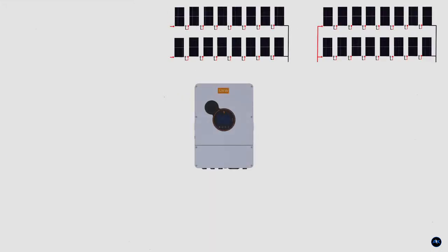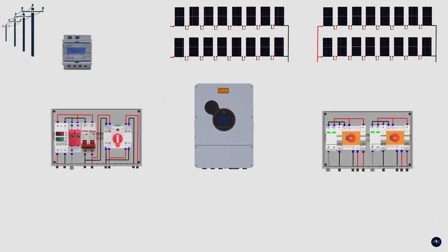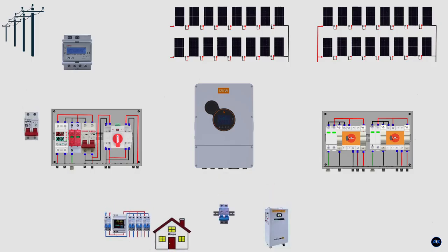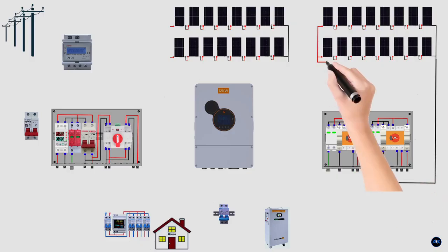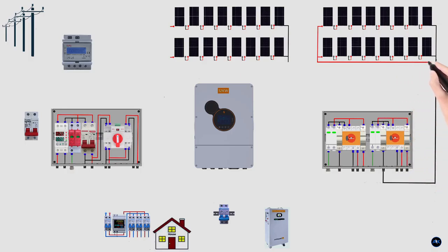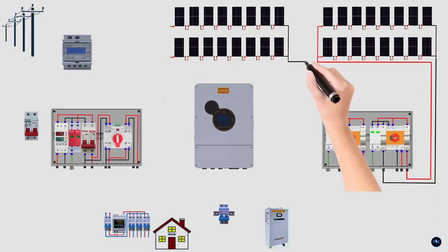Let's now connect the entire 12 kilowatt solar system step by step, starting from the solar panels and ending at the house loads. I'll explain this in a simple way, so even beginners can follow the full wiring logic safely. First, we start with the solar panels on the roof. Each solar string is made by connecting 8 580-watt panels in series. When panels are connected in series, the voltage increases, but the current stays the same.